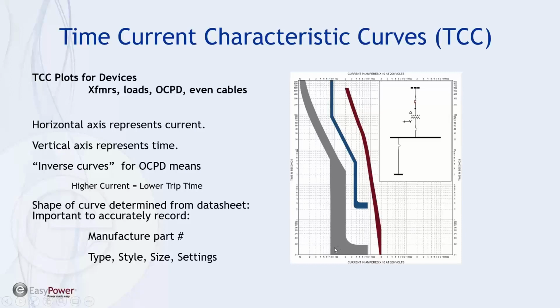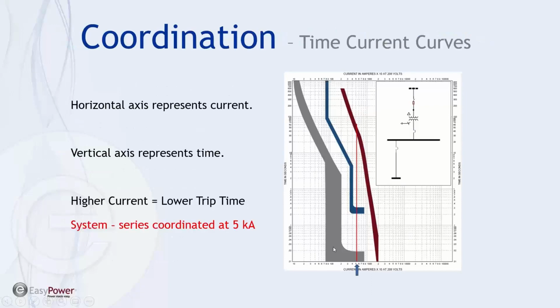If we, in our short circuit study, determined that the fault current at this bus was 5,000 amps, then we would plot that value in the vertical direction, intersecting with the 5,000 amp point, and where that curve crosses the upper or right-hand boundary of the trip curve for that protective device, that tells us what the trip time is, or what the time to clear the fault will be if that equipment were utilized.